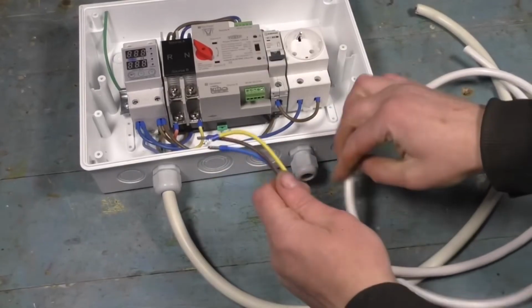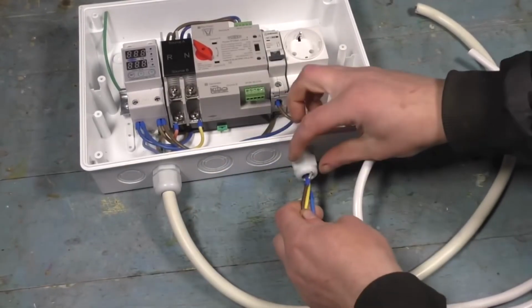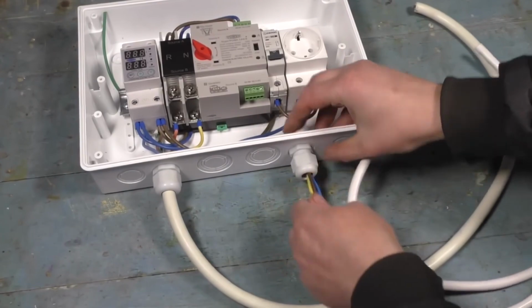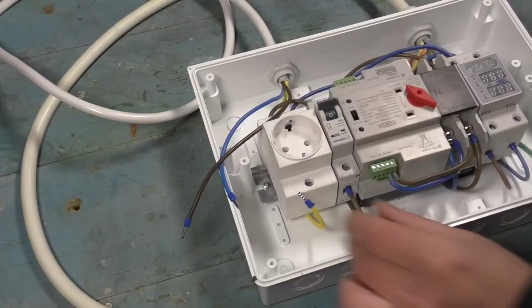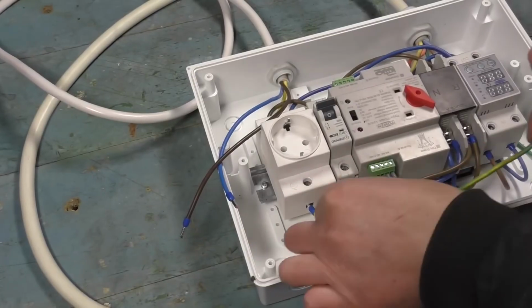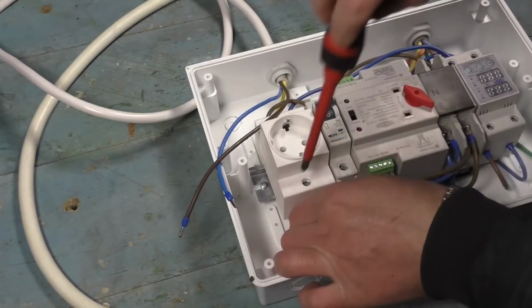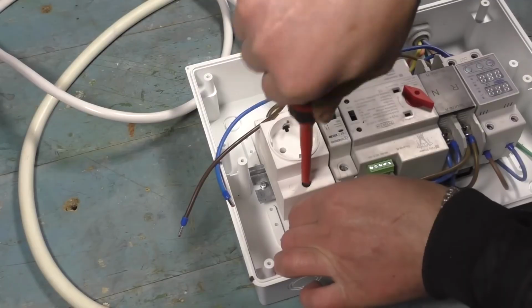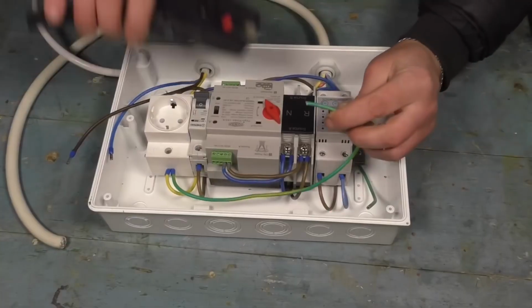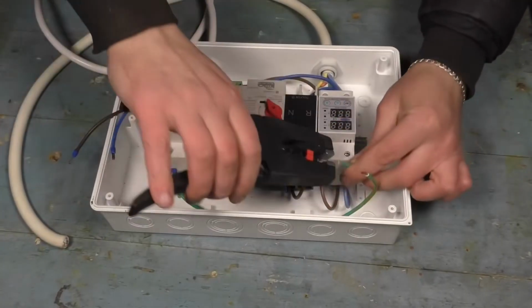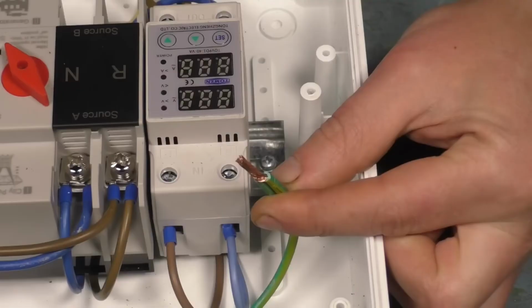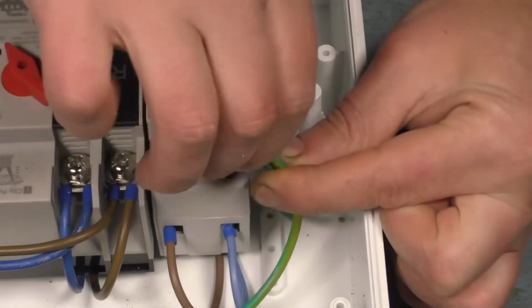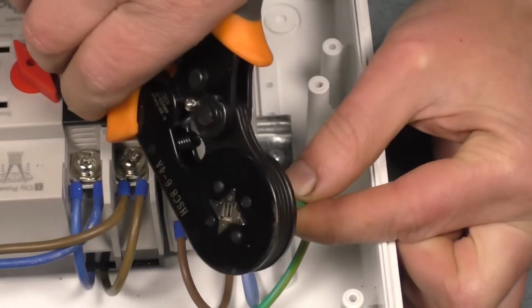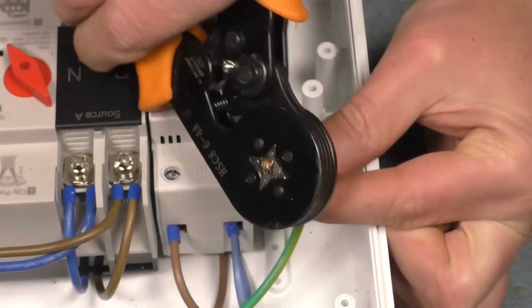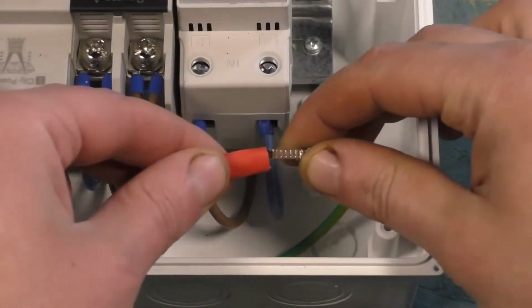Through the second input, you need to run a 3x2.5 cable, then connect 1 wire to the grounding contact of the socket, adding a jumper to it. Now this jumper needs to be connected to the free wire of the 5-core cable. I make the connection using crimping to ensure everything is secure, and then I insulate it with heat shrink tubing.